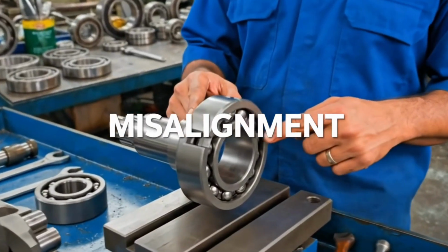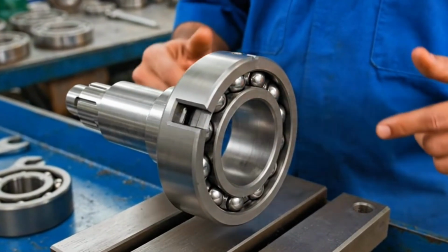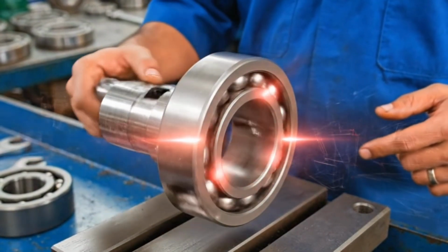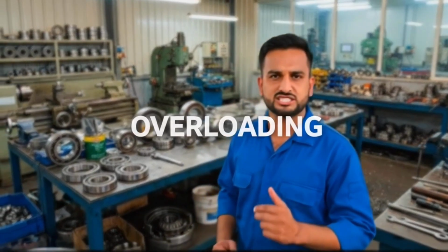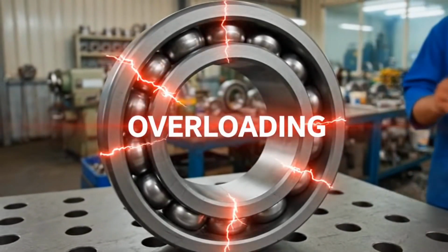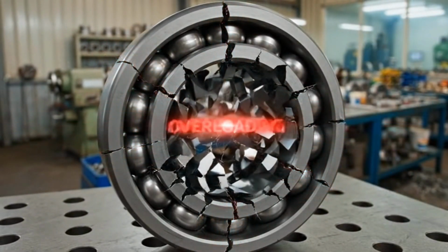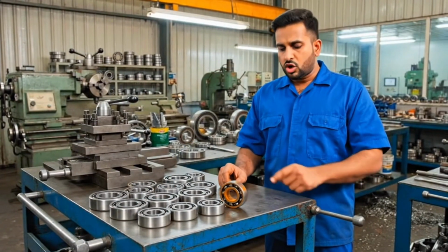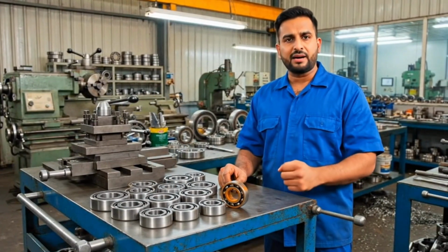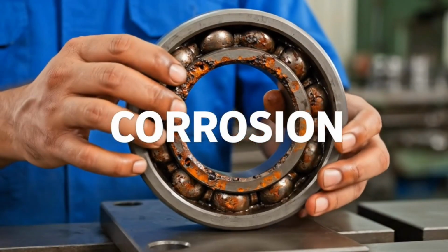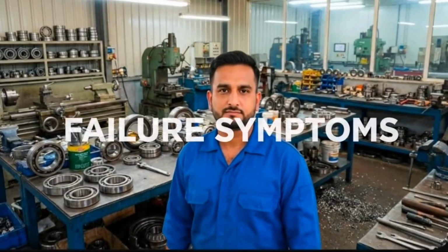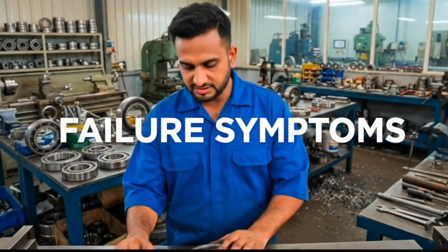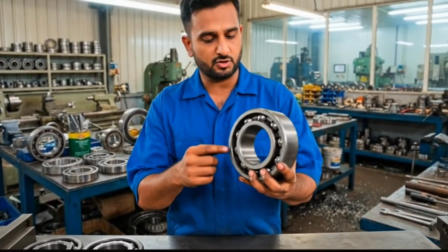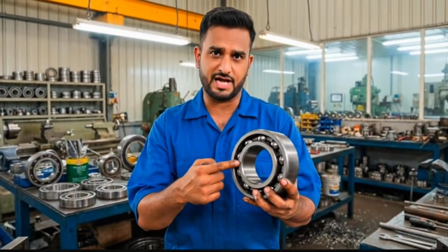Misalignment creates uneven load distribution and accelerates bearing wear. Excessive loads cause deformation, cracking, and premature bearing failure. Moisture and chemicals cause corrosion and pitting on bearing surfaces. Noise, vibration, and temperature rise are early warning signs of bearing failure.